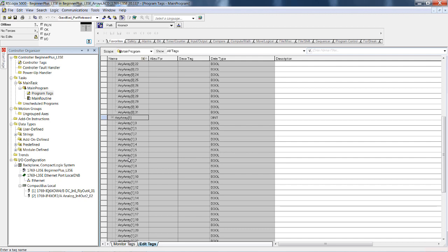That wasn't the intent with the word array. It's the number of elements of that data type, which is DINTs. Any bit instruction can address any of these 320 individual bits, and any word instruction can address any of these 10 individual words, and any file type instruction can address any group of words, any two or more words within this 10 DINT array, given that the size and boundaries are respected in how you configure a file type instruction. In this exercise, we are just going to be working with bits, but we wanted to cover some of that territory while we were in front of you.